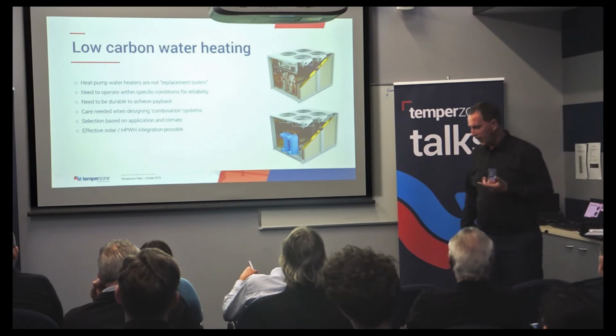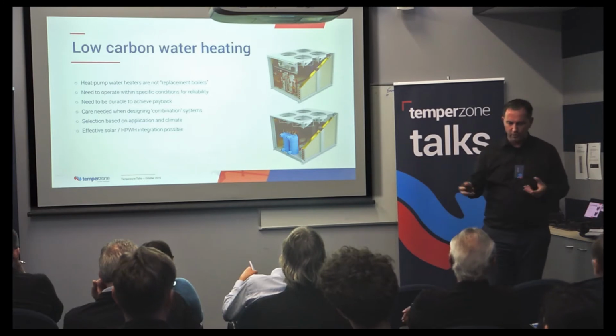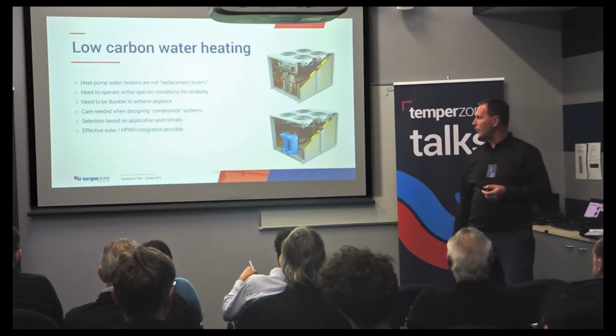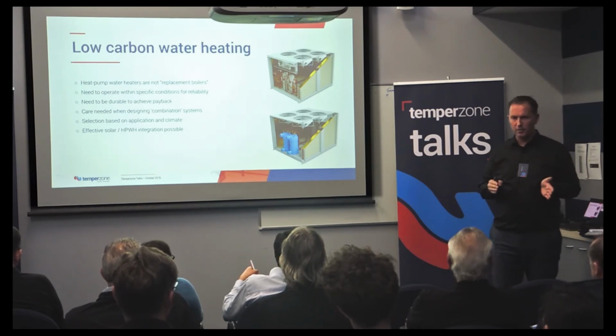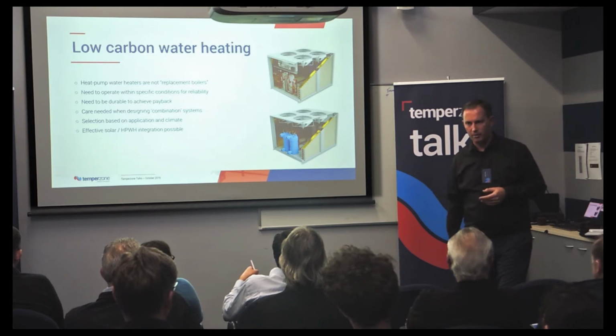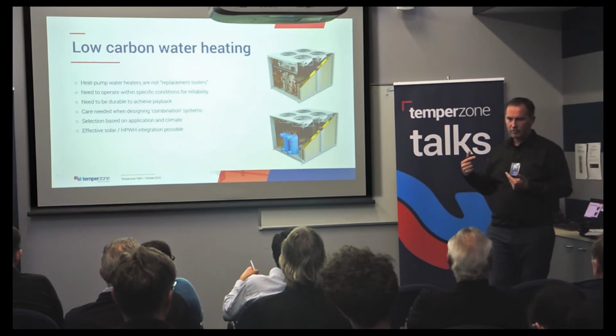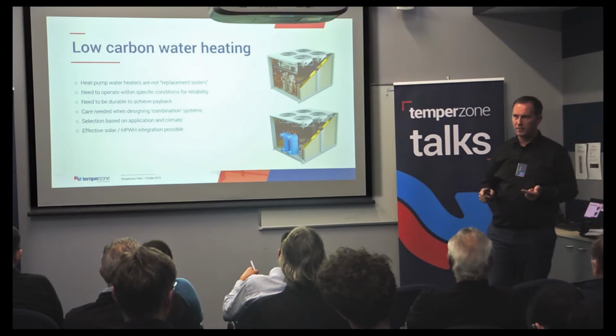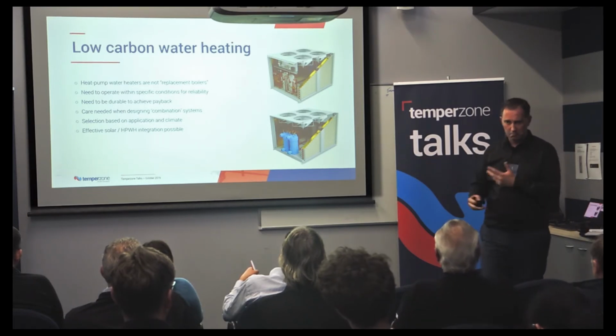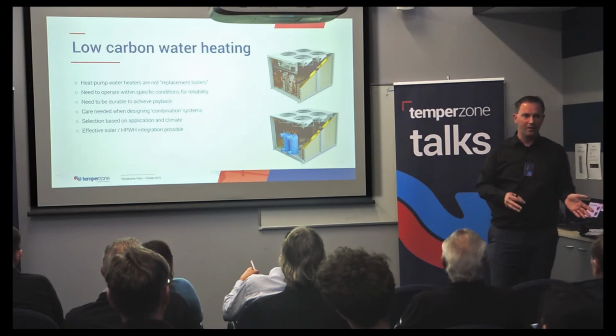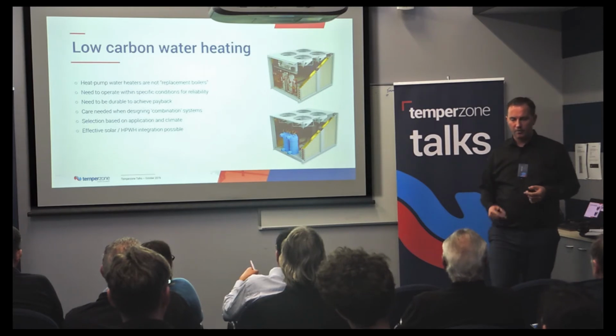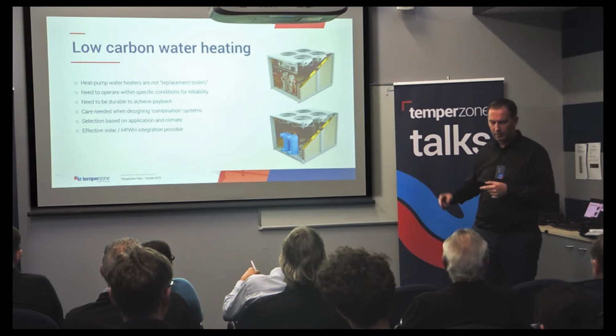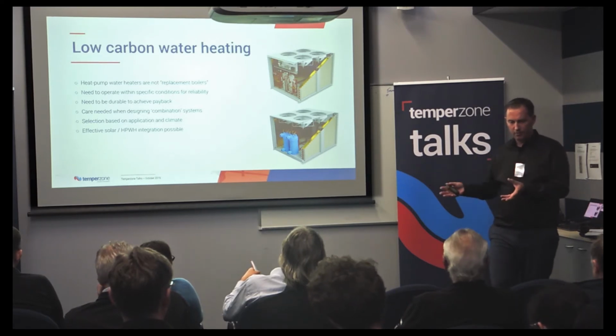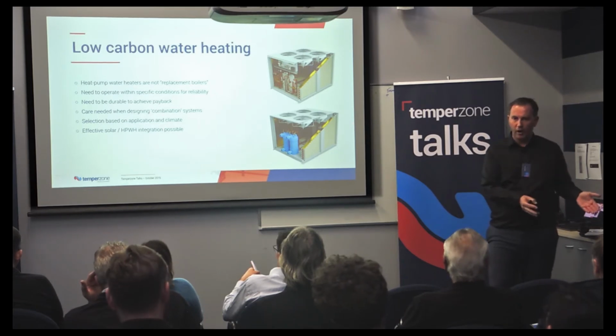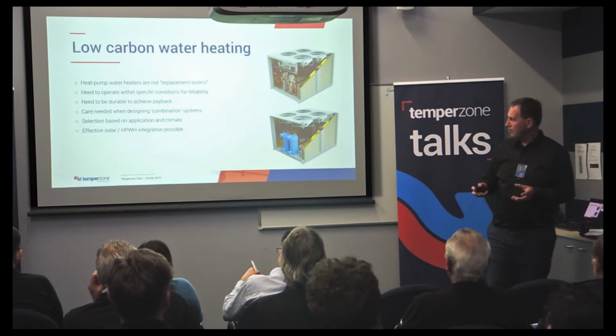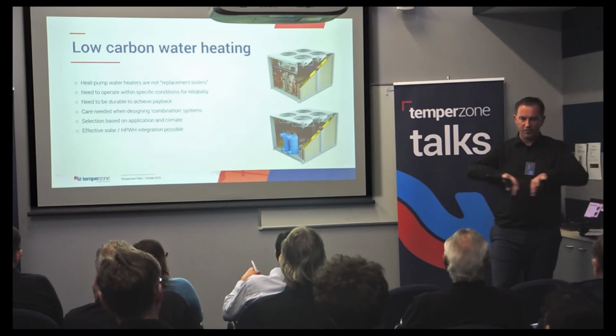Combination systems, this is where you see underfloor and potable, or pools and potable, and all these sorts of combining different temperatures with one system. And the problem with this is that you are invariably setting your system up to the highest temperature that you need, but you're degrading the performance of everything else. Now, where the main load is at a higher temperature, there's more sense to it. But very often there's this space heating and potable water heating combined, and the temperatures will be that of potable water heating, but the amount of potable water that you need is quite low, and the main load is space heating. It will be far more efficient and cost effective if you split them into two separate systems.